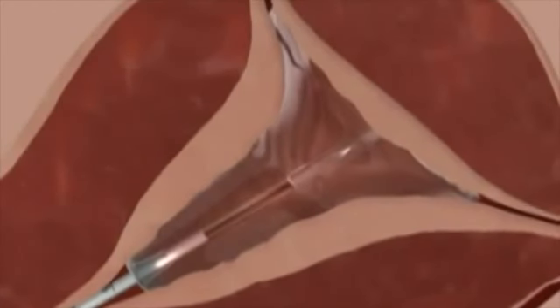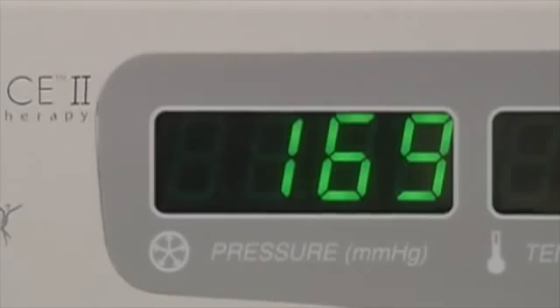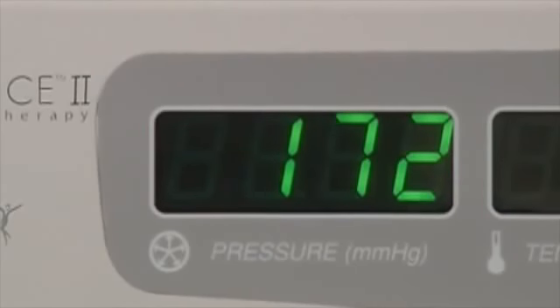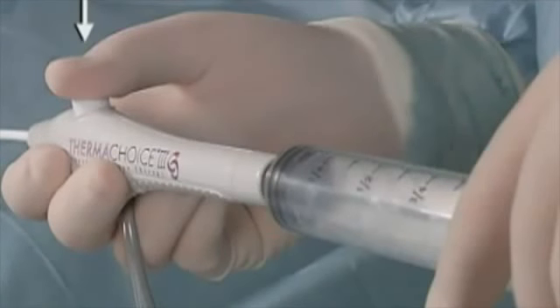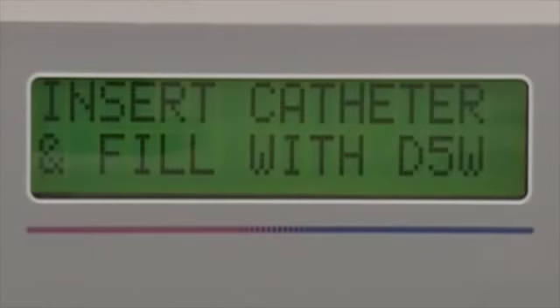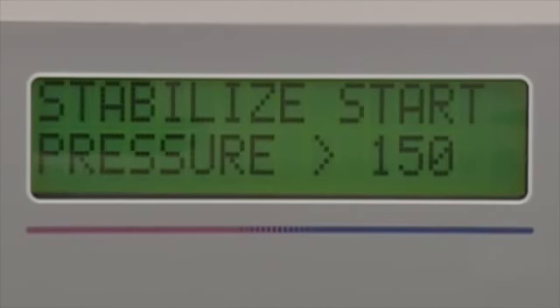The goal of pressure titration is to reach and maintain a stable pressure between 160 and 180 millimeters mercury of pressure for a minimum of 30 seconds. Note: never titrate the pressure to more than 200 millimeters of mercury, as this can later lead to overpressure warnings and even procedure termination. Also, remember to release the trumpet valve after each addition of fluid in order to stabilize the pressure. During pressure titration, the message display prompts you to fill the balloon and stabilize the start pressure above 150 millimeters mercury at a minimum.